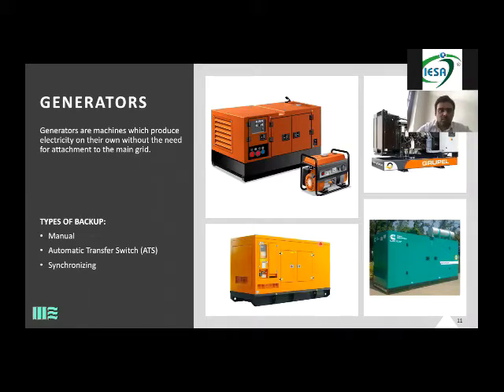So again, a lot of questions must be on gensets. How to choose the best genset on site? Again, everything comes down to paperwork. If you want to check how old the generator is, you can ask your vendor to submit the manufacturing certificates of the gensets. The life of a genset could be up to 15 years also, but it all depends on the maintenance. So the maintenance records can also be taken.